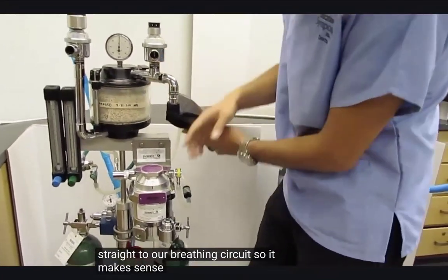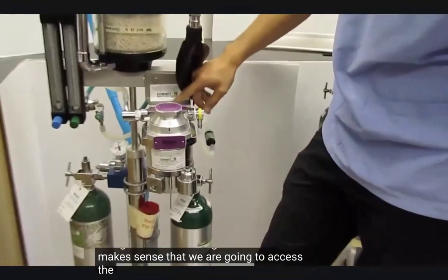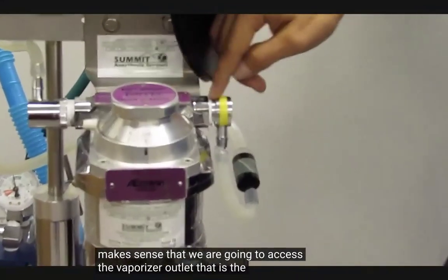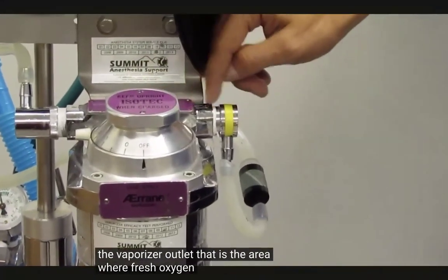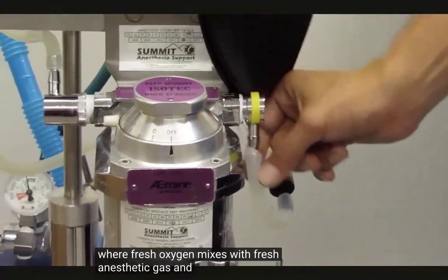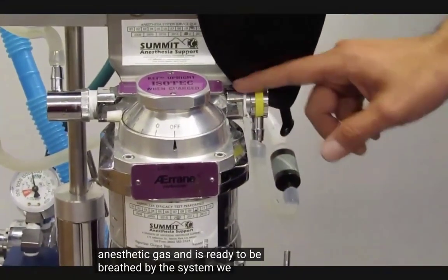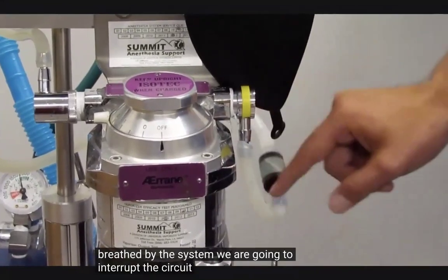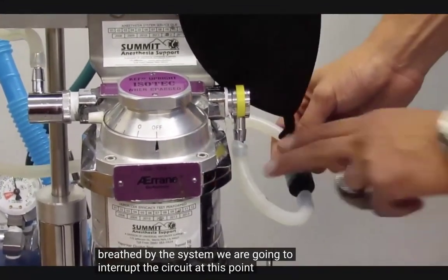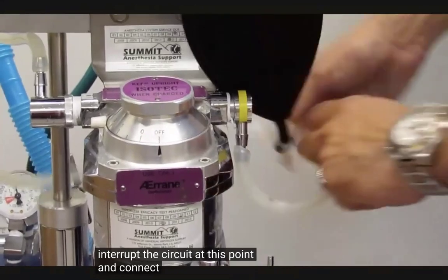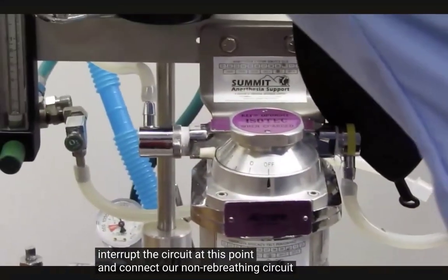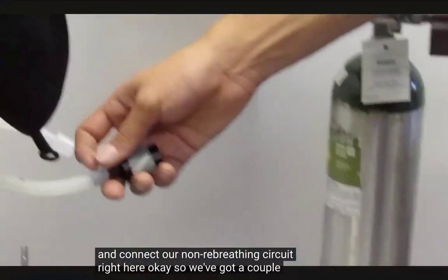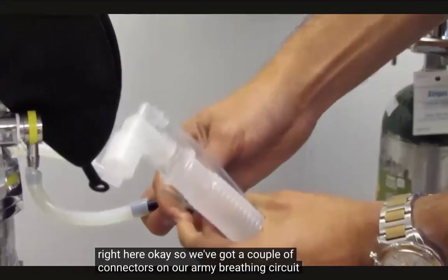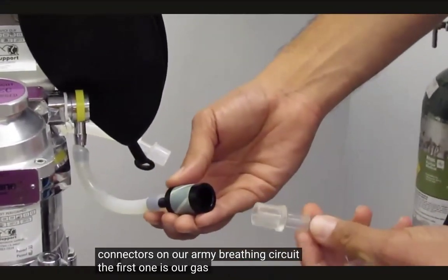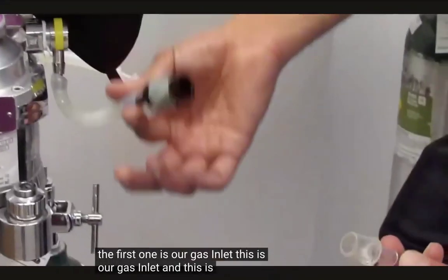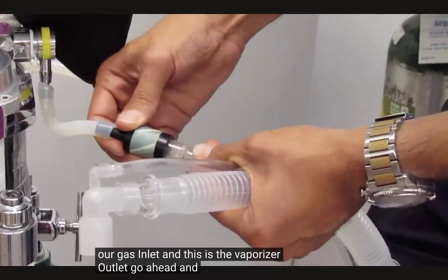So it makes sense that we are going to access the vaporizer outlet. That is the area where fresh oxygen mixes with fresh anesthetic gas and is ready to be breathed by the system. We are going to interrupt the circuit at this point and connect our non-rebreathing circuit right here. Okay, so we've got a couple of connectors on our non-rebreathing circuit. The first one is our gas inlet. This is our gas inlet, and this is the vaporizer outlet. Go ahead and connect that.